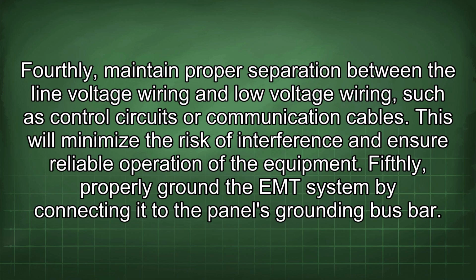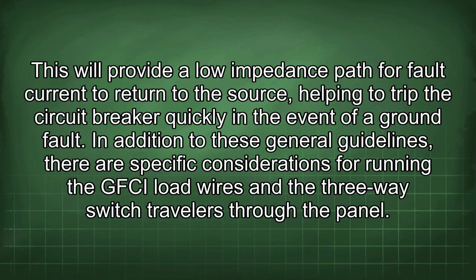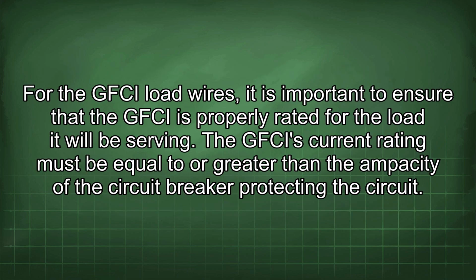Fifthly, properly ground the EMT system by connecting it to the panel's grounding bus bar. This will provide a low impedance path for fault current to return to the source, helping to trip the circuit breaker quickly in the event of a ground fault. In addition to these general guidelines, there are specific considerations for running the GFCI load wires and the three-way switch travelers through the panel. For the GFCI load wires, it is important to ensure that the GFCI is properly rated for the load it will be serving. The GFCI's current rating must be equal to or greater than the ampacity of the circuit breaker protecting the circuit.